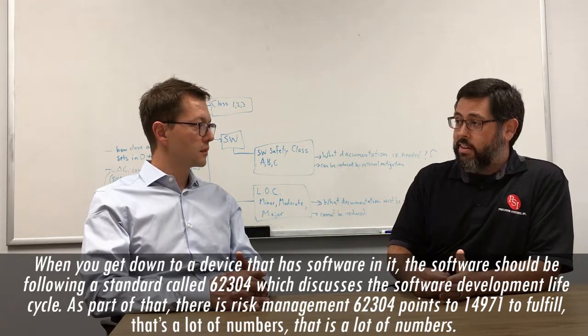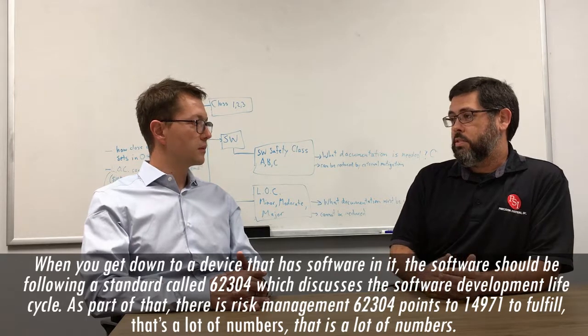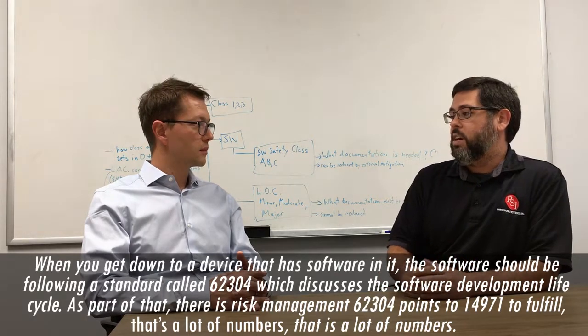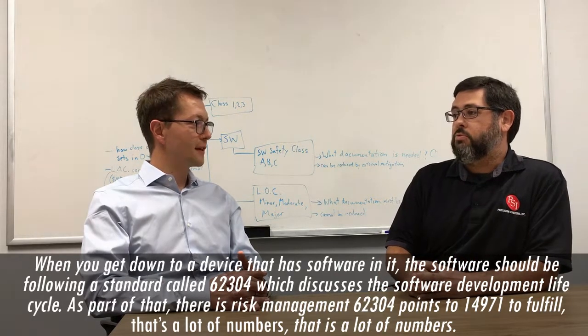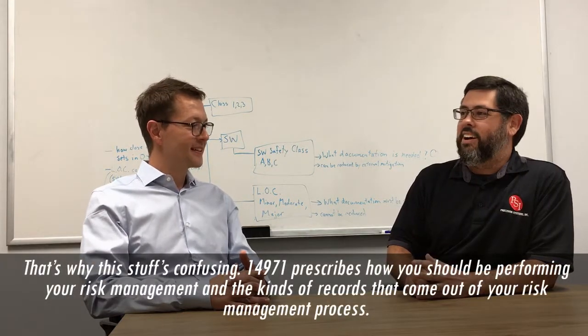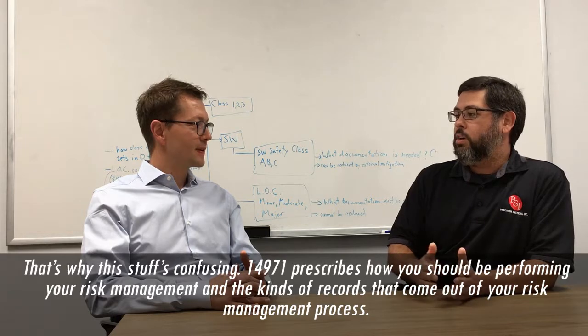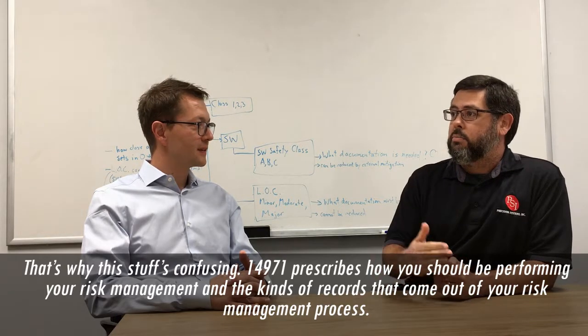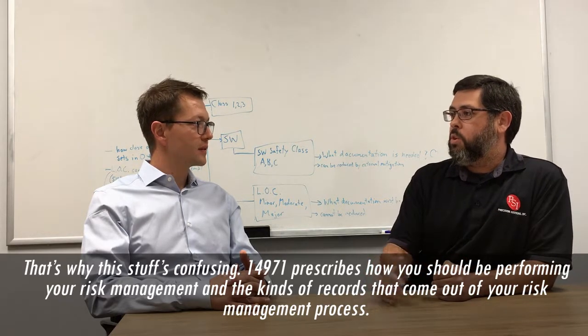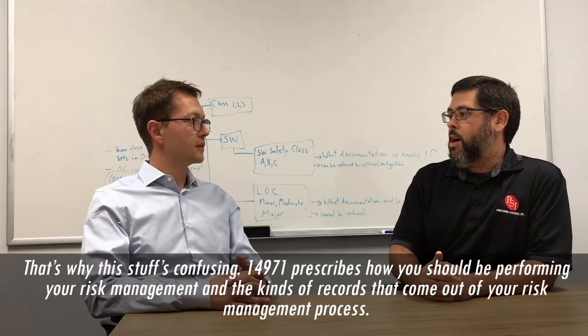As part of that, there is risk management. 62304 points to 14971 to fulfill that. There's a lot of numbers. Yeah, that's why this stuff's confusing. Yeah. 14971 prescribes how you should be performing your risk management and the kinds of records that come out of your risk management process. Okay.